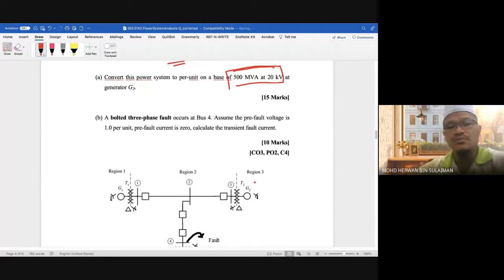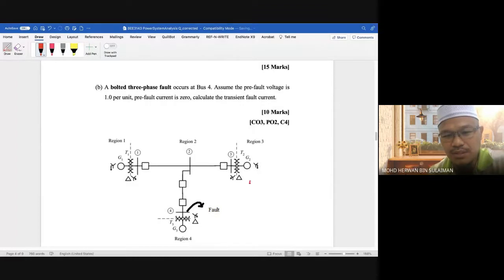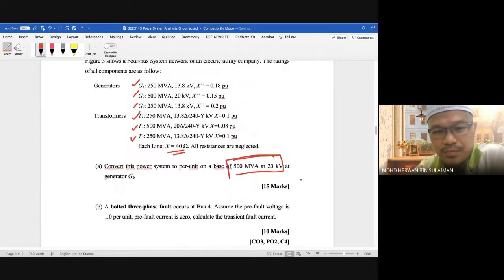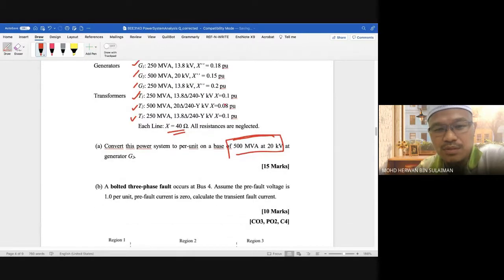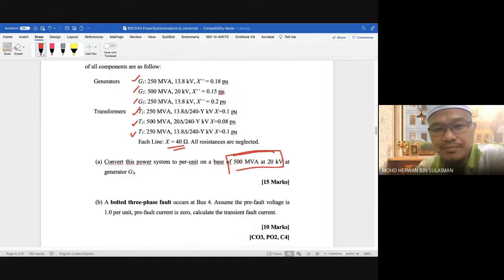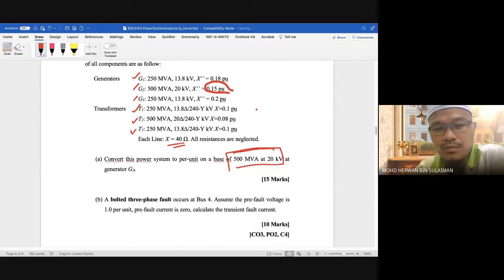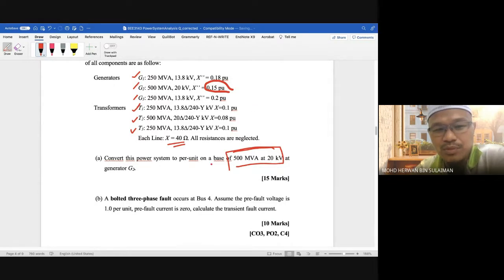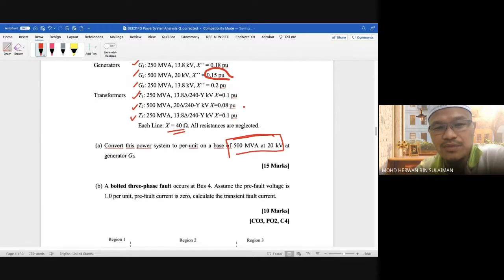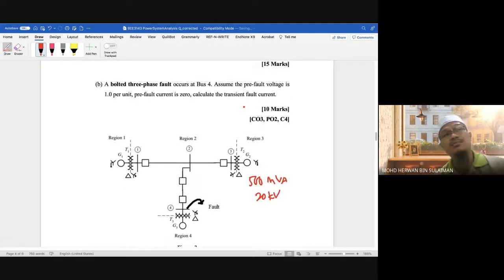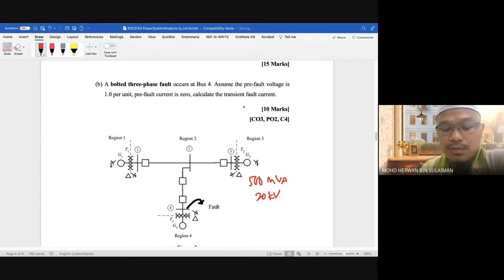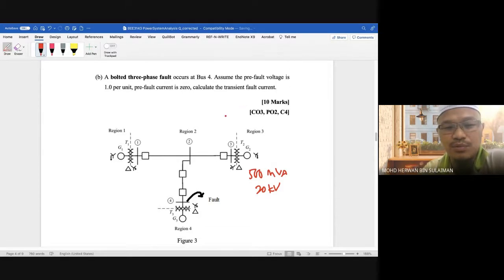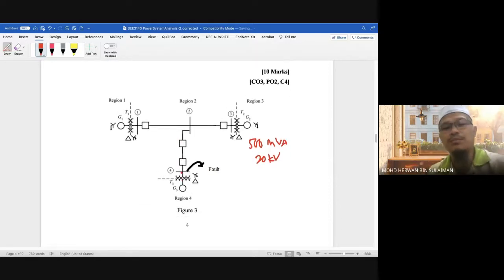Alright, so the base here is 500 MVA, 20kV. The rating at G2 is 20kV, so we take that as our reference. Since this is a positive sequence analysis — the question doesn't mention unbalanced fault — we only look at the positive sequence. So what you need to do is convert this diagram into an impedance diagram.